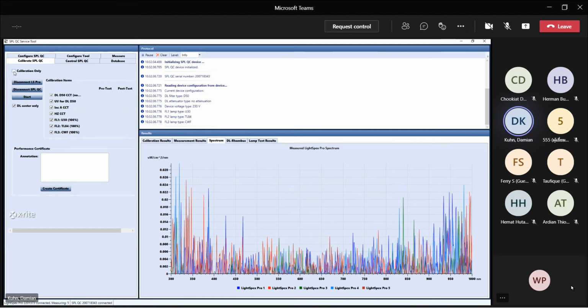One is if you would like to take pre-test readings before the software actually starts adjusting the lamp voltages to get the correct color temperature. That's the standard setting, so we document for the customer how the performance was before adjusting the lamp voltages.